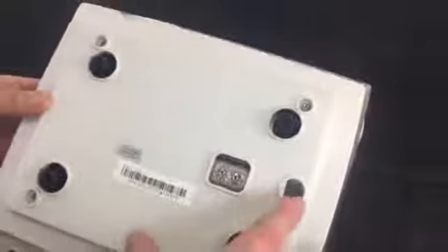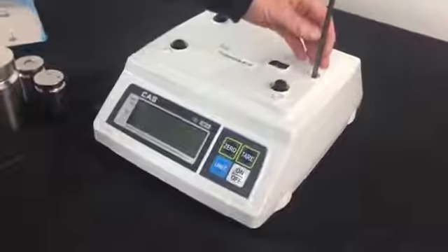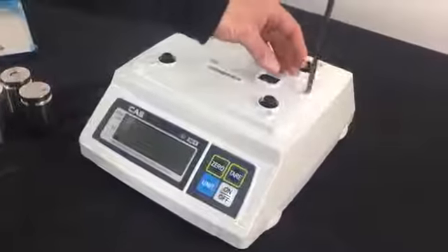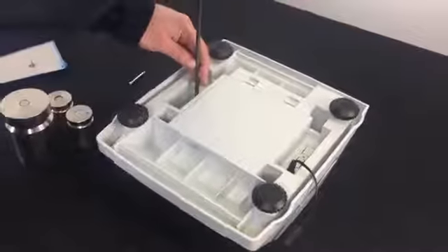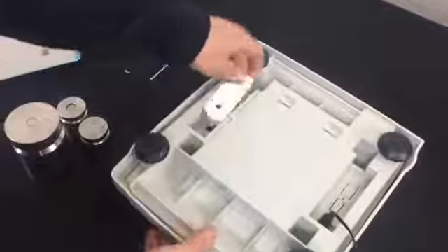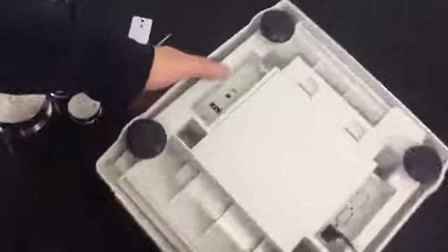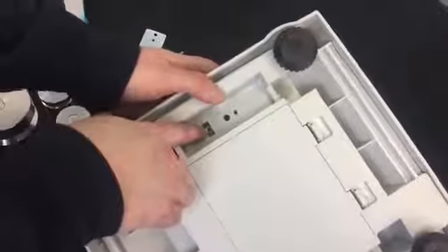Right here, there's a screw at the bottom. This is to remove the calibration plate, which is located underneath the scale. So after we remove this screw from the top, we want to flip that around, get this screw out, and you'll see that there's one more screw located underneath to hold this plate in. Now, we go ahead and we remove this screw in order to get rid of this plate that's in here to access that calibration switch right in there.